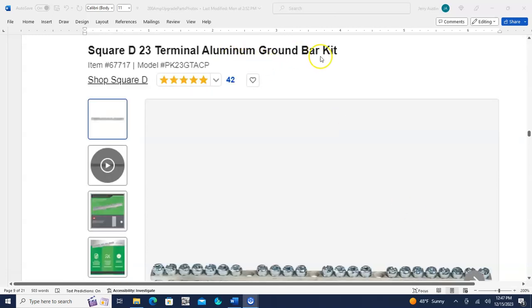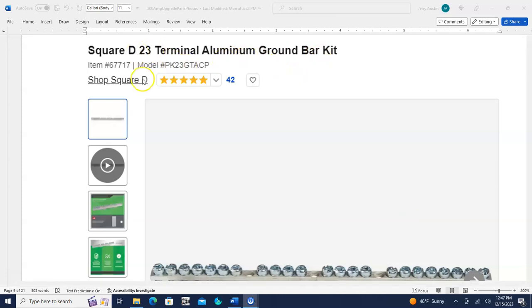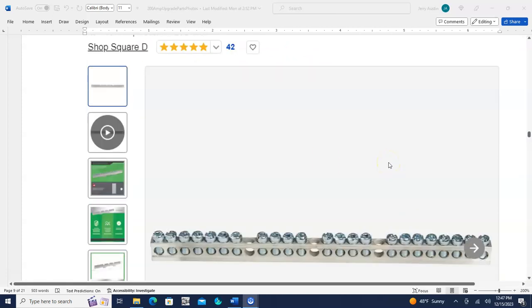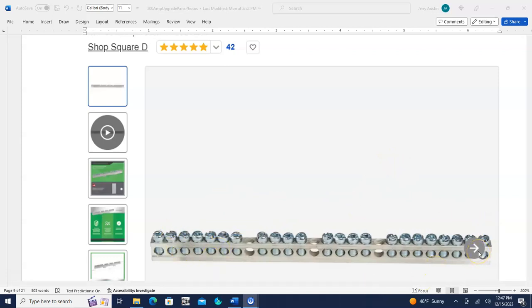This is a ground bar kit. The code on these new electric upgrades is that you have to have a separate bus. This is called a bus because it's got a lot of places on it, just like a bus has a lot of seats for passengers - this is the electric safety bus. The circuit breaker box comes with a bus on each side of those circuit breakers for the electrical neutral, but now you have a separate bus in these boxes used only for the electric ground wires.